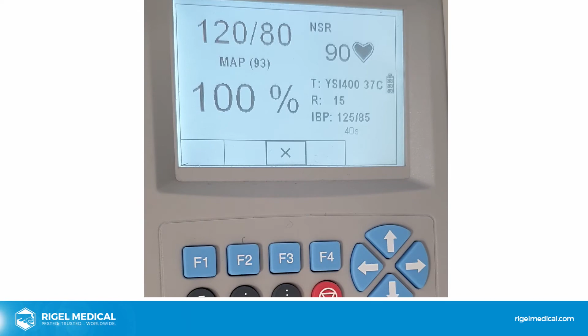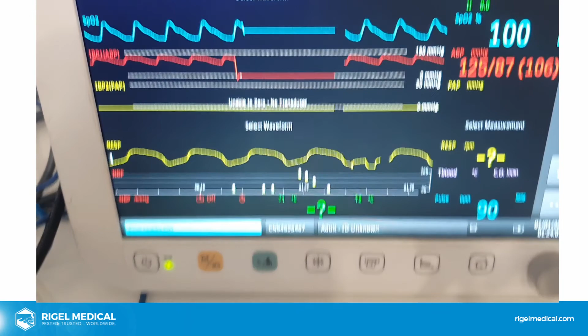So we've got 125/87 for IBP, 106, 100% SpO2, 90 beats per minute and 15 respirations per minute at 37 degrees. That's pretty much what we'd expect. A little bit high on the IBP, but probably in spec for this particular monitor. So that simulation is now complete.